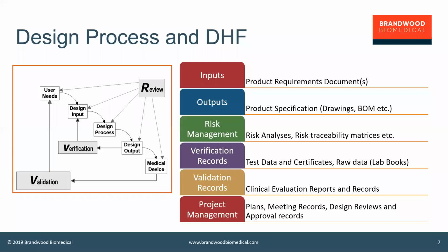And then the last thing, and this is kind of the overarching thing that ties this all together, is the project management. Again, the expectation of the regulator is that at every stage, there is some type of review so that you have an understanding as to where you're progressing with the design and development of your device, but that you've addressed all of the required documentation and any of the risks that are associated with each of those stages of development. So how do you show that? You show that with your overall project management plan. You show that with design meeting records. So when your XFT meets and has conversations about this, you also show it with your design reviews.